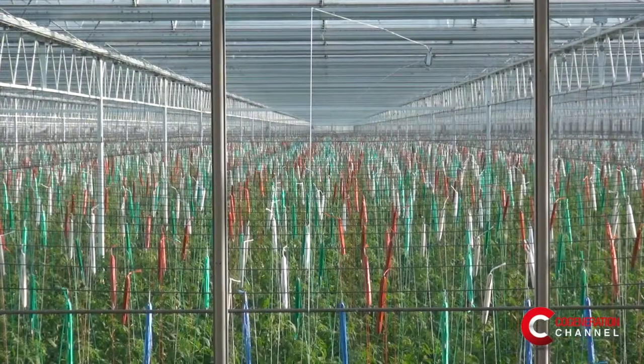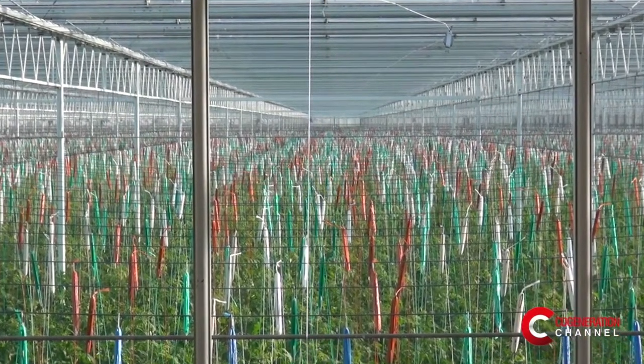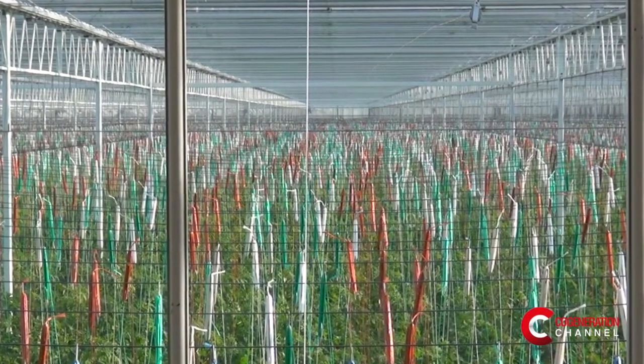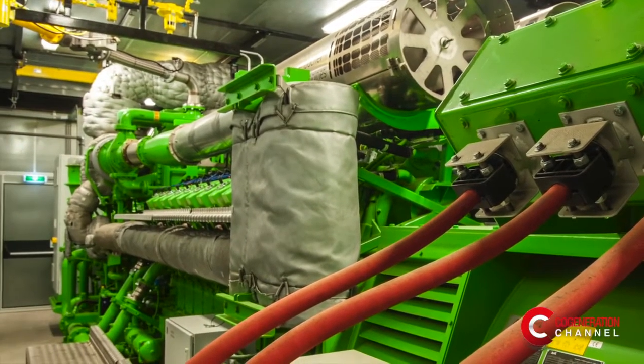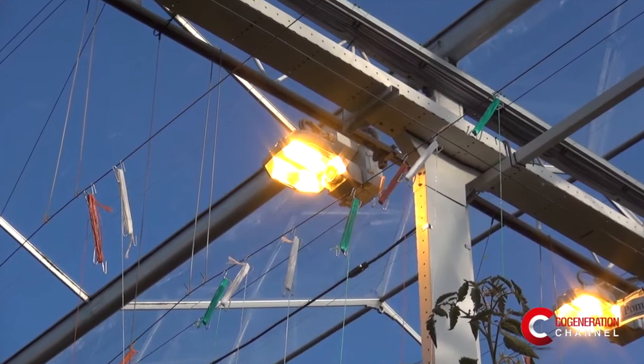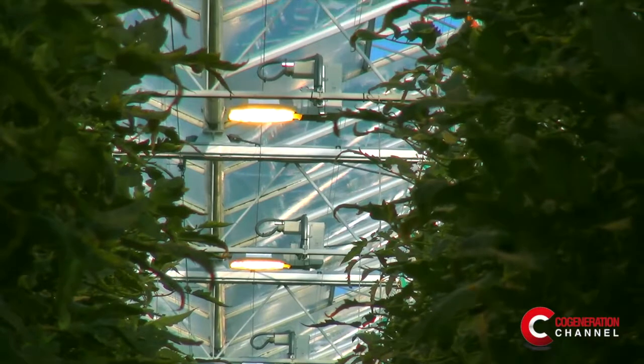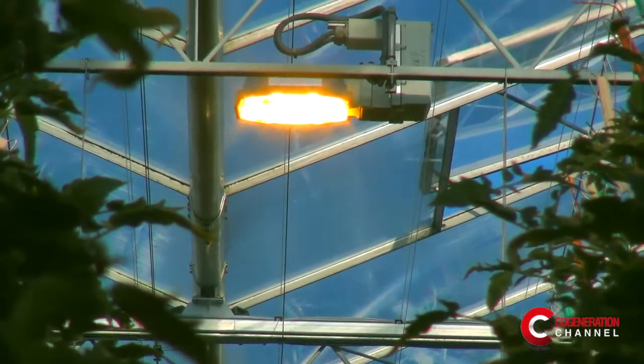This is specifically to produce tomatoes in the winter time. Here you can see one of these greenhouses — a 6 hectare block, 60,000 square meters with one variety, Roma variety, a plum tomato. We need 6 megawatts to light this whole area, about 1 megawatt per hectare. We use our cogeneration units for about 4,000 to 4,500 running hours per year, and 2,000 of these will be for artificial lighting.